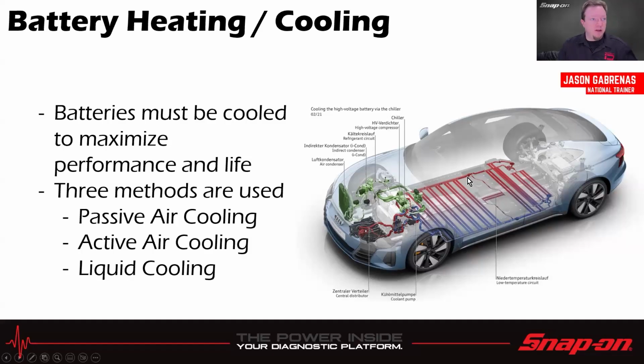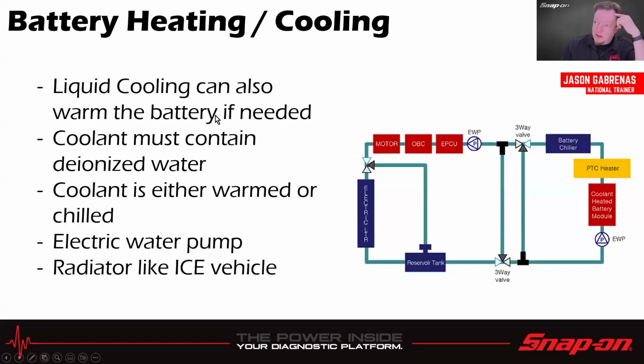When they do have liquid cooling, it could also warm the battery if needed, depending on the situation and the outside temperature. In this case, this one has a heater or a chiller, and then there are multiple valves that direct the coolant where it needs to go. Coolant must contain deionized water because we want it to be less of a conductor. Ionized water would conduct electricity much better. So the special coolant that they use in these systems contains deionized water. And the coolant is either warmed or chilled by a heater or chiller.